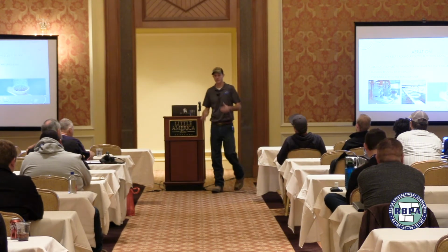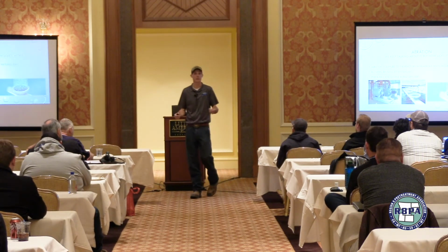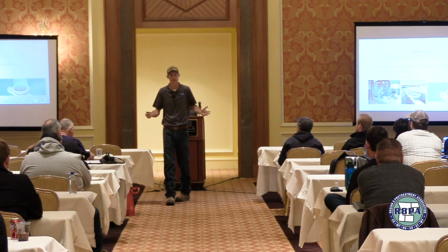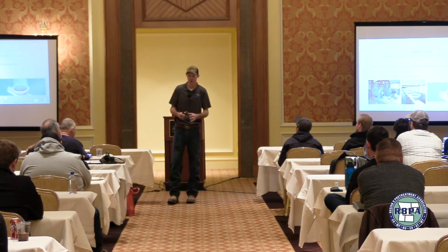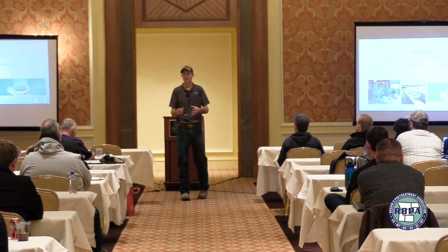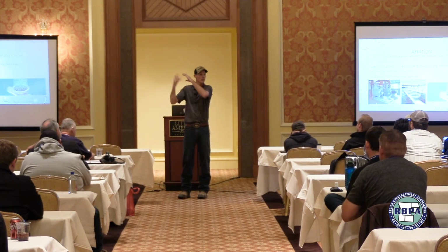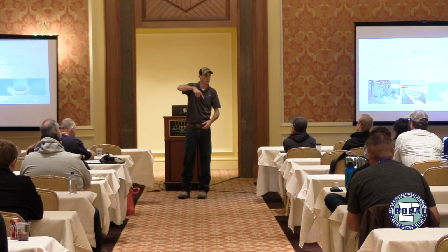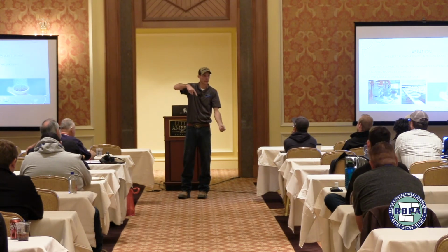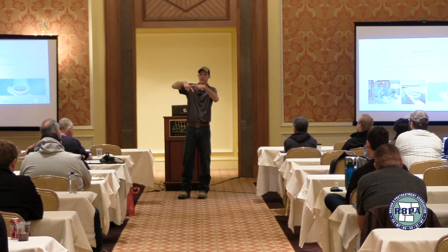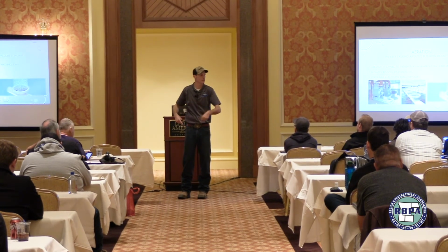So a jet system is a simple, really cool, old tried and true design. Basically a centrifugal pump. Everybody's seen a centrifugal pump. Instead of the standpipe going up to pump the water out, it goes into a little nozzle and it introduces air. As the water flows through the nozzle, there's a hole in it, an orifice plate, and that air is sucked in and creates oxygen.